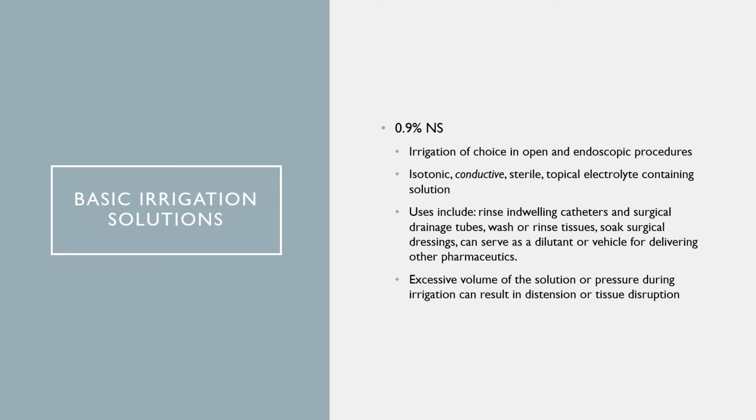However, in endoscopic procedures, the electrosurgical unit is applied within the fluid confined space, so other irrigation solutions that don't have conductive properties need to be used. Okay, so we want to try and not use normal saline with the ESU.